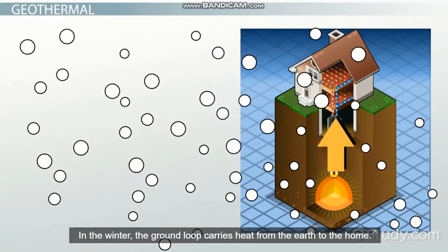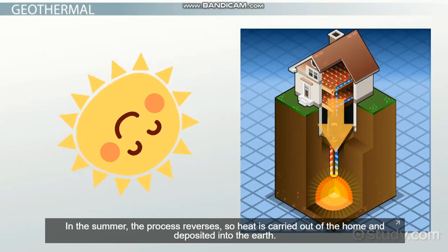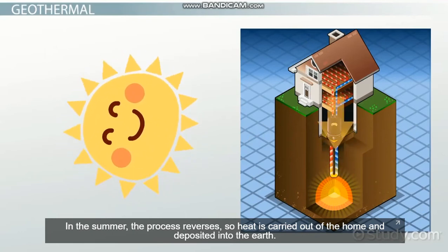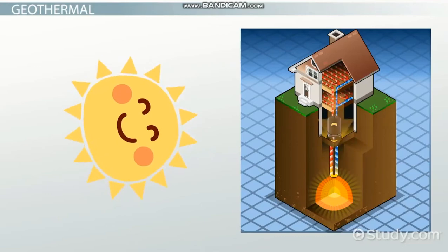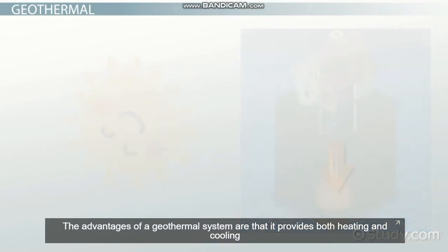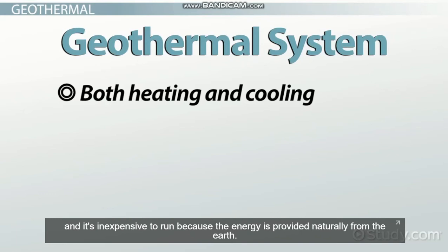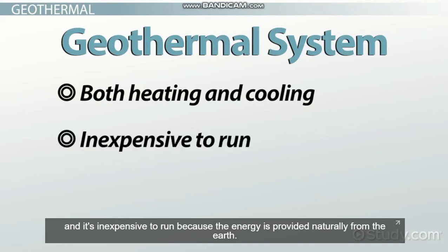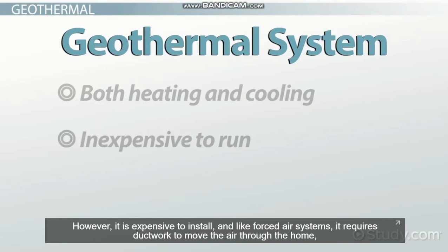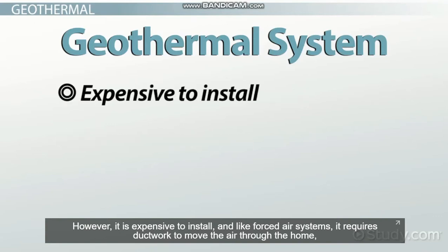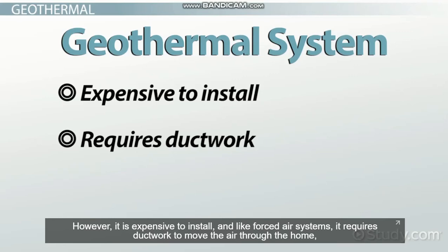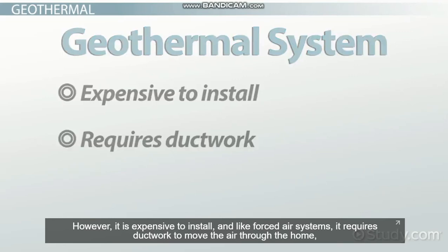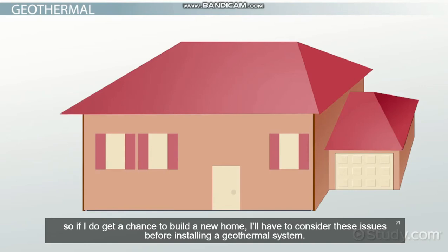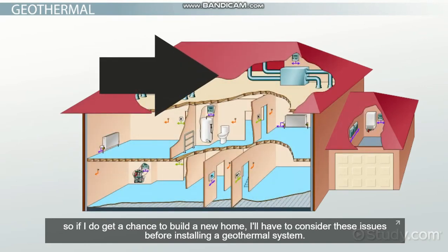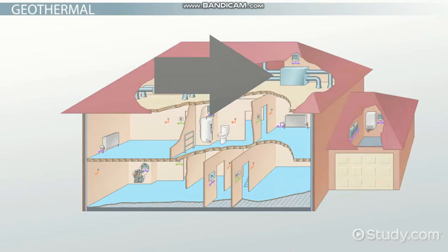In the winter, the ground loop carries heat from the earth to the home. In the summer, the process reverses, so heat is carried out of the home and deposited into the earth. The advantage of a geothermal system is that it provides both heating and cooling, and it's inexpensive to run because the energy is provided naturally from the earth. However, it's expensive to install, and like forced air systems, it requires ductwork to move the air through the home. So if I do get a chance to build a new home, I'll have to consider these issues before installing a geothermal system.